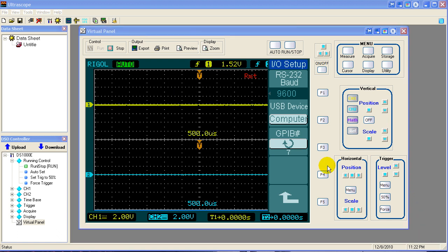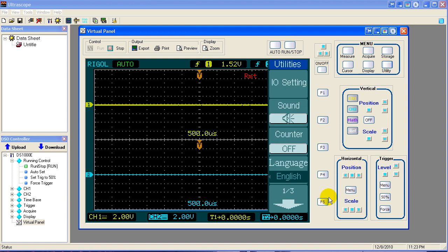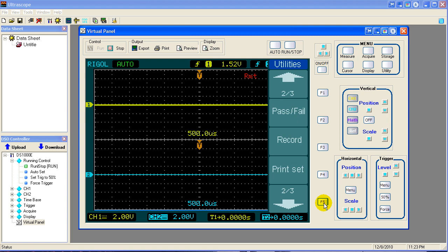Okay, now that I've disconnected all the input signals, I'm going to the utility menu. And we'll scroll down the next page. And I hope it's on this page. Self-calibration right here. It says remove the inputs, I did. I didn't worry about alternate sweep or anything like that, so see what happens. So press F3 to do self-calibration.